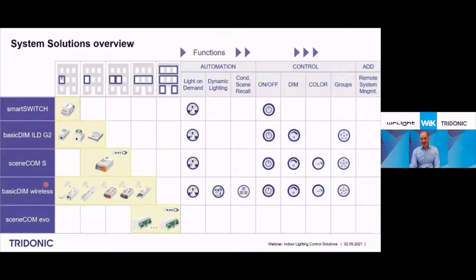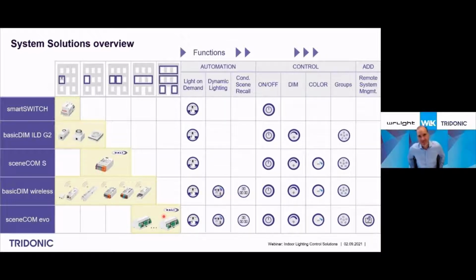And with sceneCOM Evo, that is really our solution for big installations, entire buildings, multiple buildings. Here we have sceneCOM Evo in our portfolio, offering more or less everything around light management systems and lighting automation, from human-centric, emergency, single battery controlled report handling, event triggering. We have a logbook and error book so we see over time where there are problems in the field with LED drivers and LED boards, and we are implementing all the D4i and DALI, the new extended DALI information, DALI parts 251, 254, where you get information about the luminaire, under voltage, over voltage, how the driver is acting, what was programmed. That is all now coming into our sceneCOM Evo lineup.